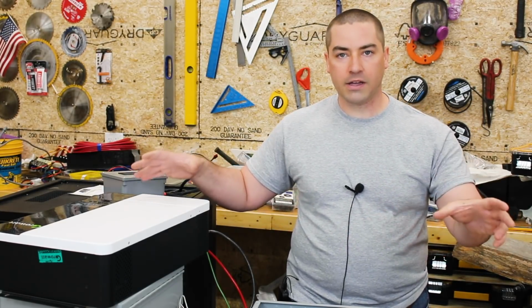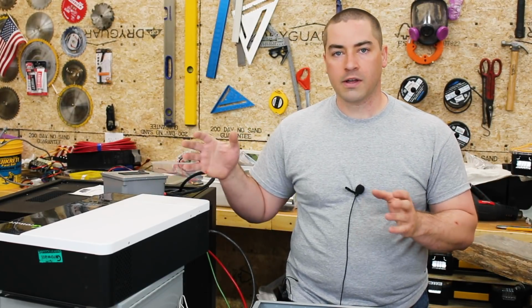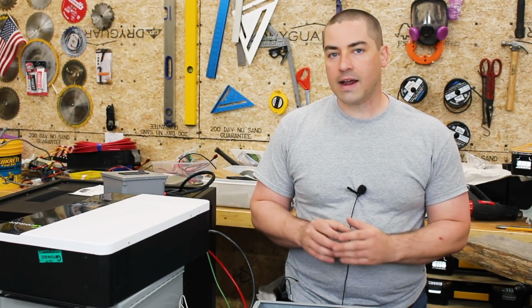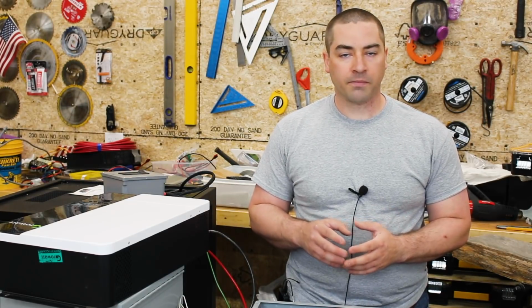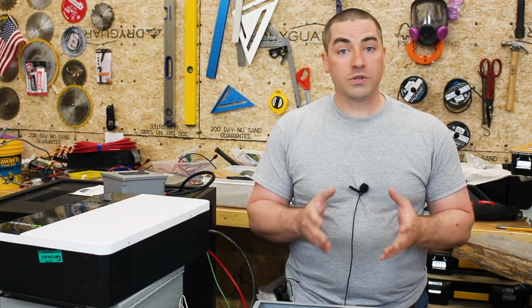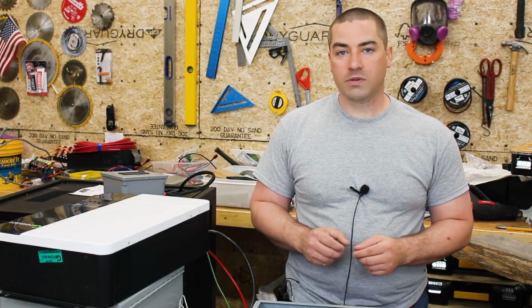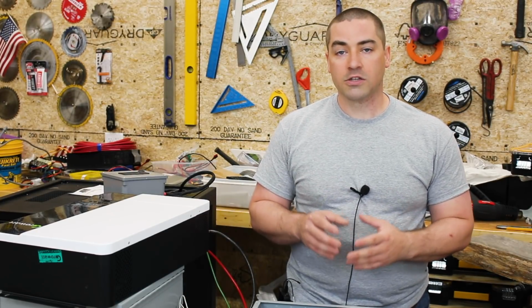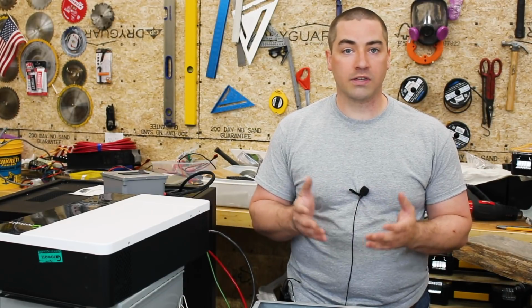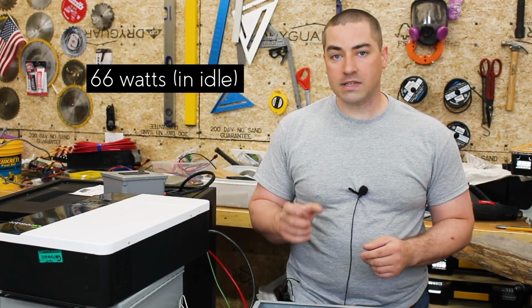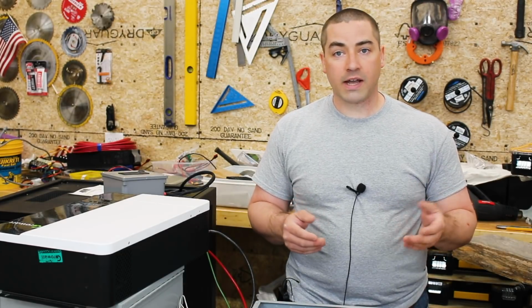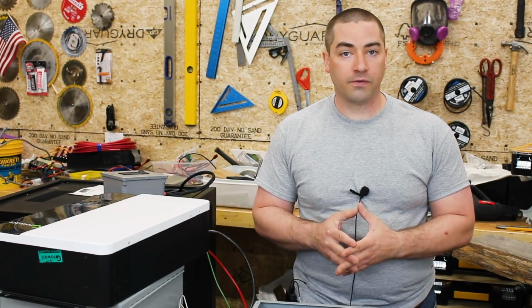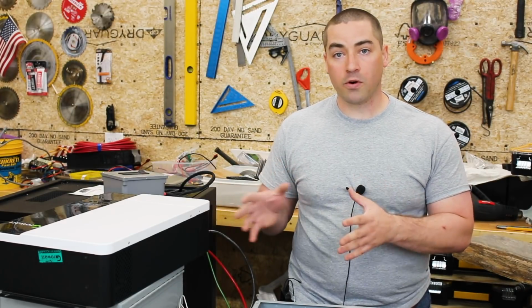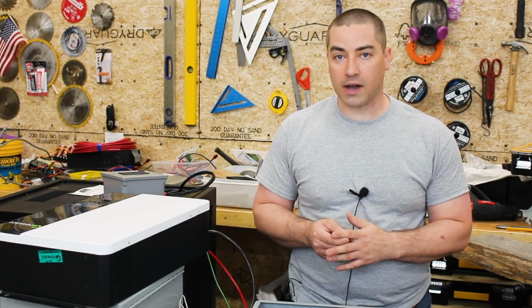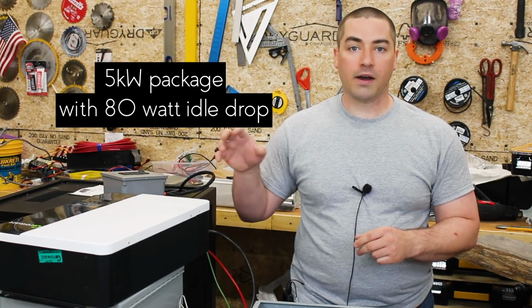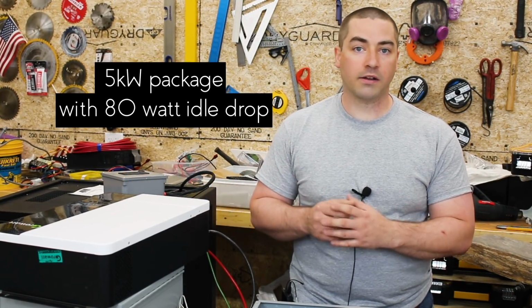But let's look at the package of auto transformer with inverter, and that was 80 watts. Now that's not as efficient as some other options out there. To put this in perspective, I used to own an AIMS brand low frequency inverter that had a transformer built in, so it already put out the 120/240 split phase. That was 66 watts in idle. You can check out the link in the description below to that old video where I tested that. Now that would have been more efficient because that was 6 kilowatts with a 66 watt idle. And this package is a 5 kilowatt package with an 80 watt idle draw.